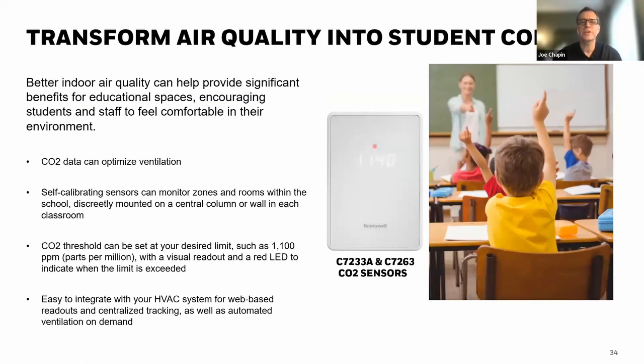So you're transforming your air quality into student comfort. Better indoor air quality can provide significant benefits for educational spaces. CO2 data can optimize ventilation. It can self-calibrate with this device, and your threshold can be whatever limit you want, say 1,100 parts per million. It can have a readout where you see here 1,140, when the red dot indicates that's not good. But it's also very easy to integrate into an existing system. Again, remember, when you put a Niagara system in place and connect one of these devices, it automatically goes into discovery mode, picks up the devices, brings them in and identifies them.